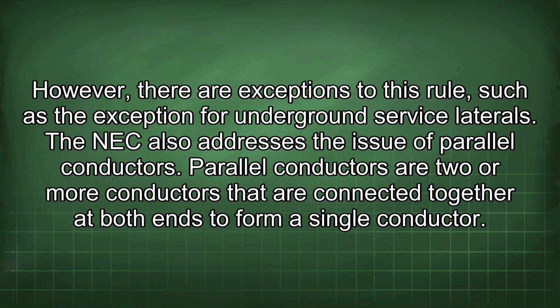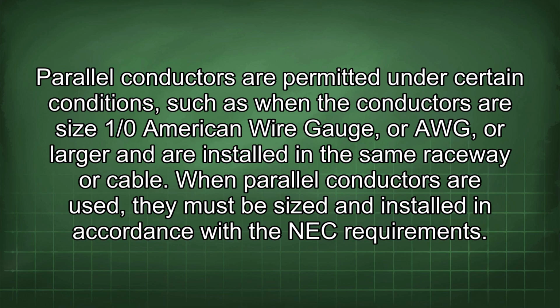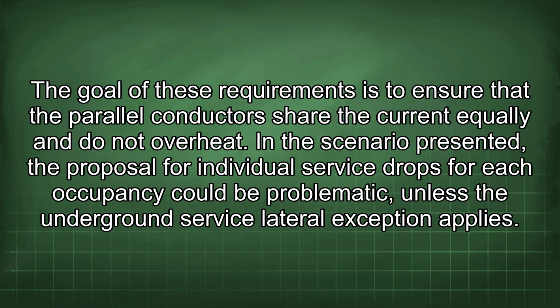The NEC also addresses the issue of parallel conductors. Parallel conductors are two or more conductors that are connected together at both ends to form a single conductor. Parallel conductors are permitted under certain conditions, such as when the conductors are size 1/0 American wire gauge, or AWG, or larger and are installed in the same raceway or cable. When parallel conductors are used, they must be sized and installed in accordance with the NEC requirements. The goal of these requirements is to ensure that the parallel conductors share the current equally and do not overheat.